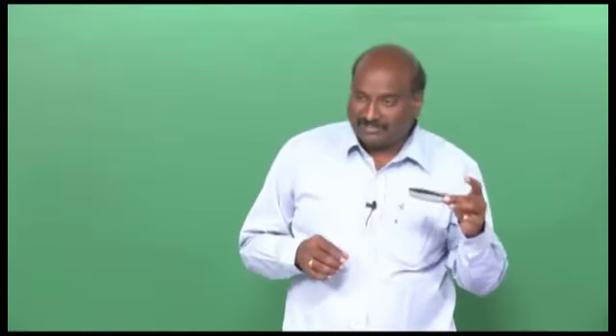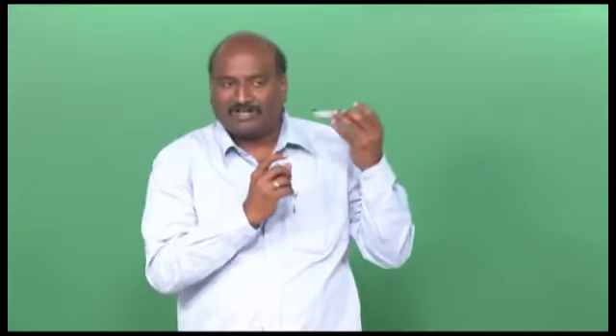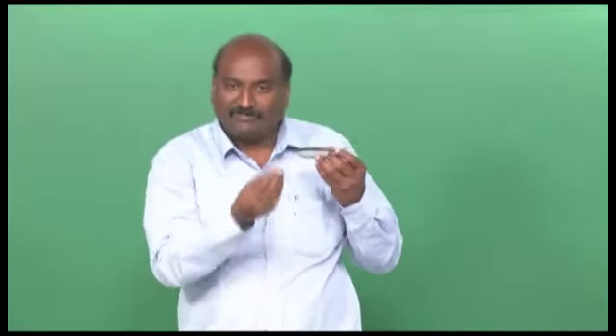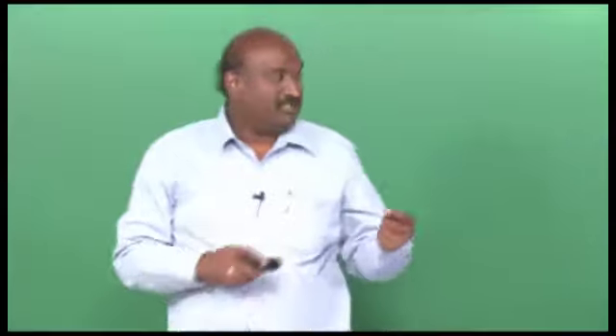When you design an equipment, you cannot say that you have completely sealed it. Take for example a jam bottle or any bottle: when I twist it and close it, there is always some gap, less than 1 mm or 0.5 mm. For a vapor, this gap is more than sufficient to go inside. That is what you call the safe gaps available for those types of products. If you are going to handle hydrogen, it is more critical, the gap available will be totally different, and the construction also would be different.